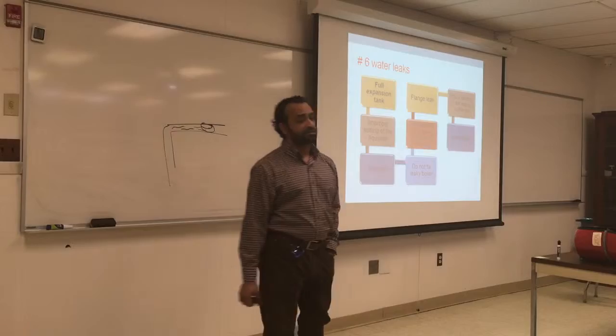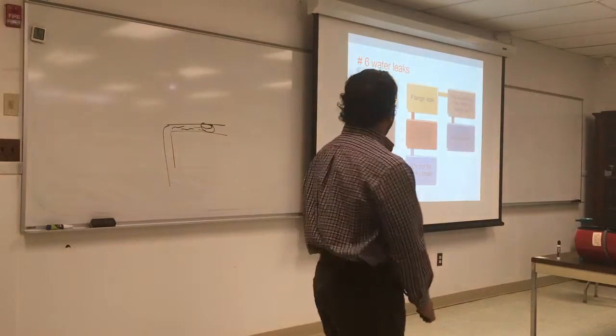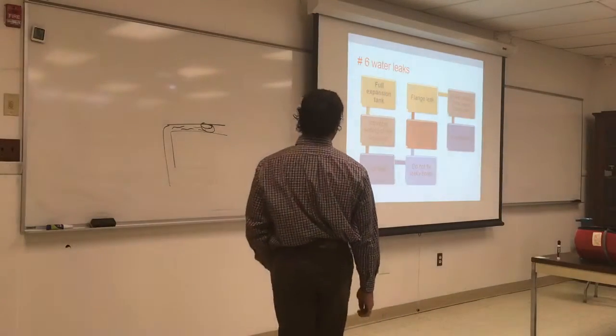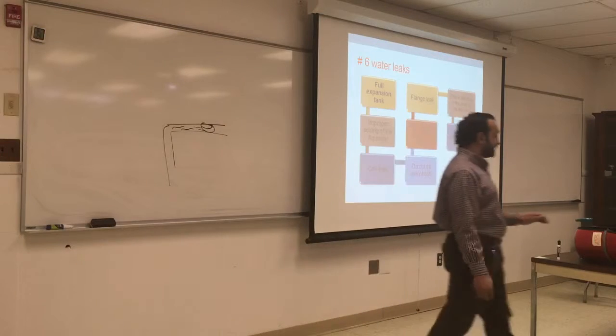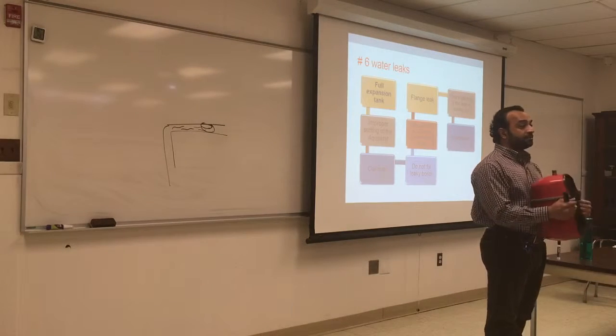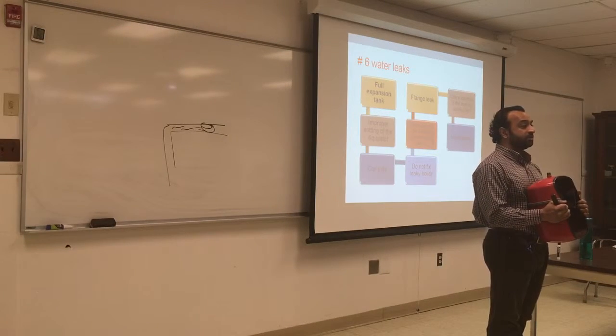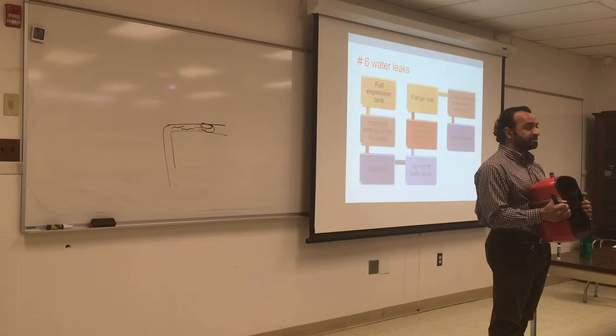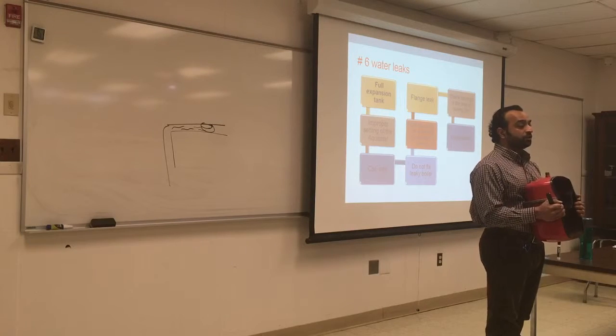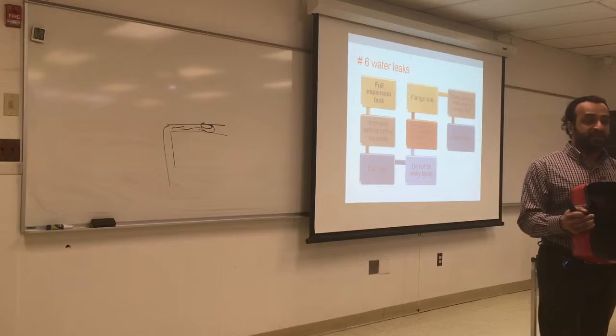If you have water leaks, the first thing you check is the expansion tank. This is the expansion tank. And in the other class, AST205, we will learn how to size this expansion tank for this purpose, so you do not undersize the water expansion tank.